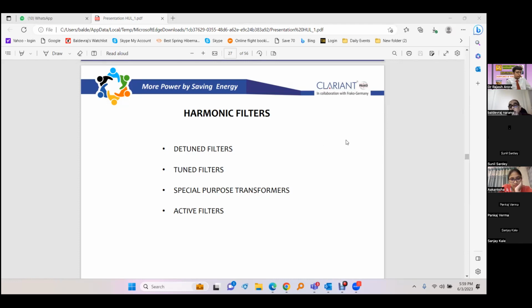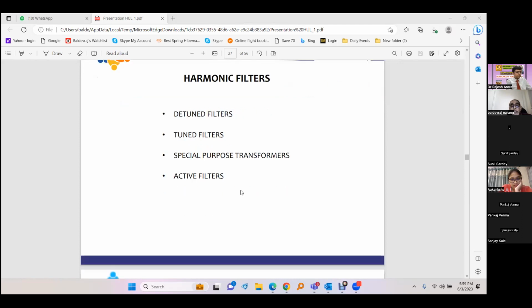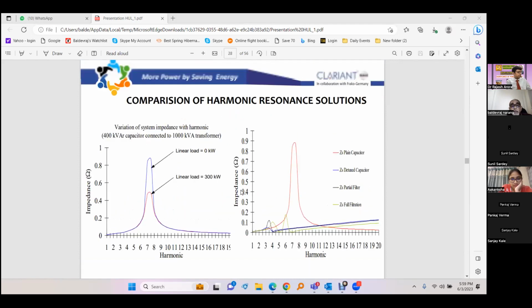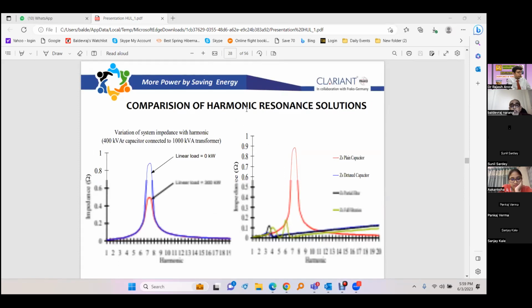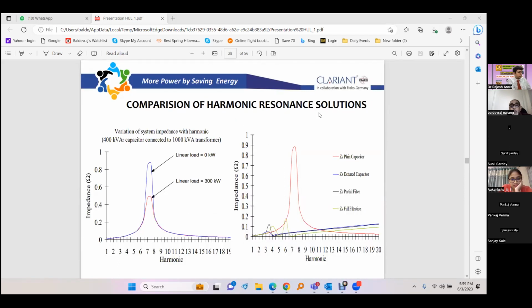It has limbs in opposite direction, where the third harmonic gets cancelled against each other. And then the third harmonic is totally removed from the system. Then active filters we have. So before we go to that, I'll just explain how the resonance was being shifted to a safe place with the passive unit.